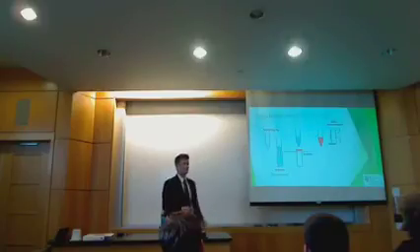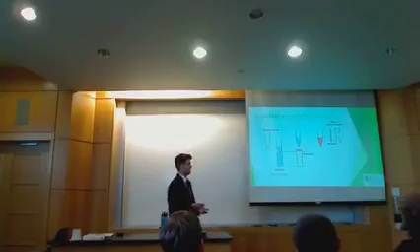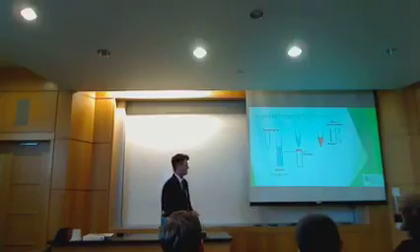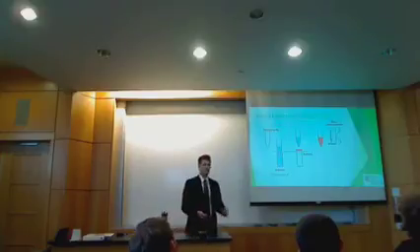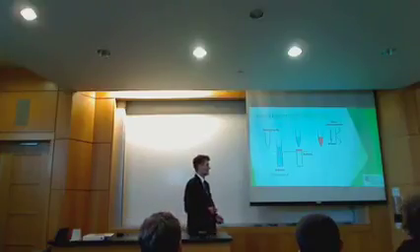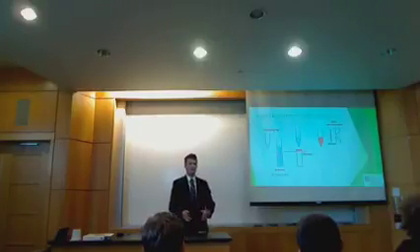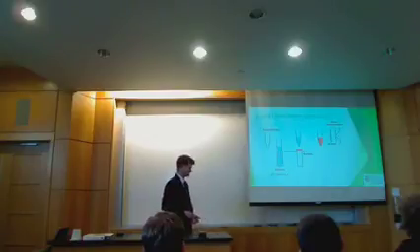So here is the actual liquid extraction surface analysis technique, which was developed at the laboratory I was in, the Organic and Biological Mass Spectrometry group. What we do is we have a robotic arm which selects a new sampling tip for each sample, draws up a specific amount of solvent, approximately 100 microliters. Then it moves over to the spot in question, which we specify using a computer program, and it will automatically dispense the solvent onto that sample, wait a certain amount of time at the surface, draw the sample back up, and then inject it into the mass spectrometer.